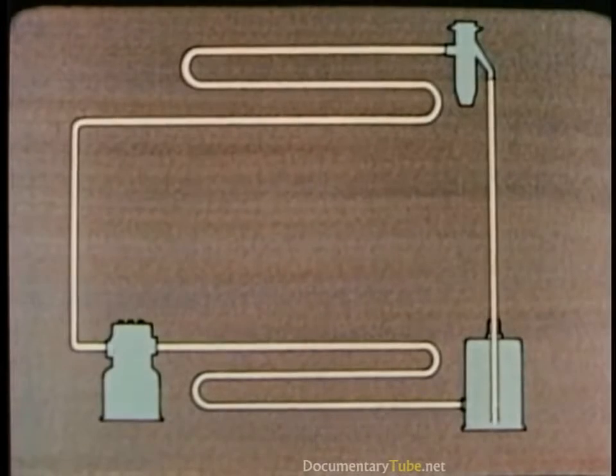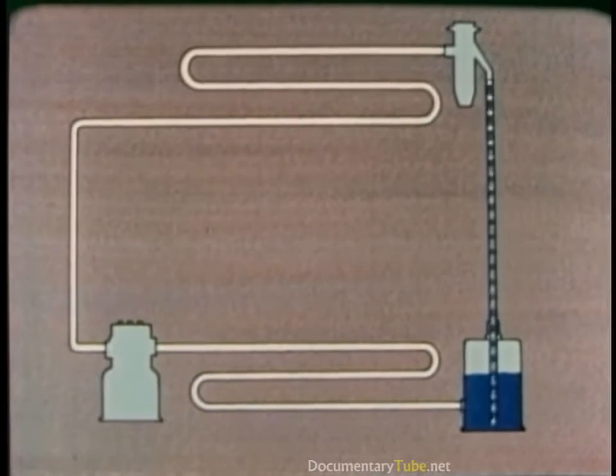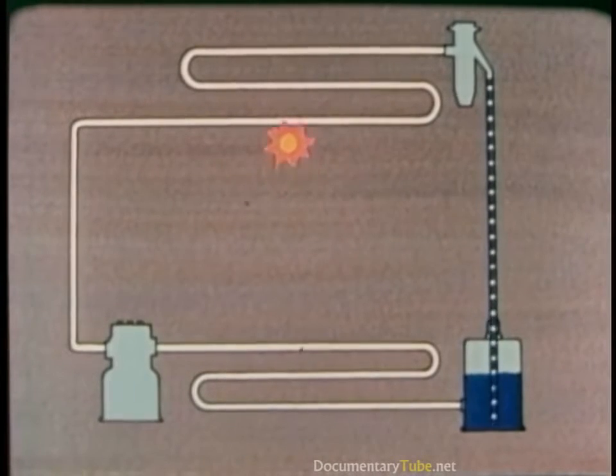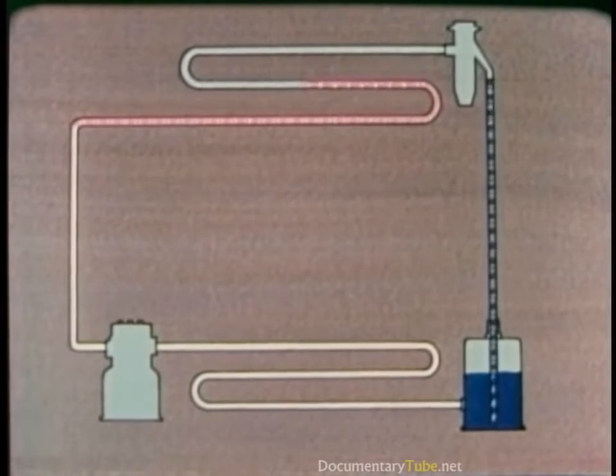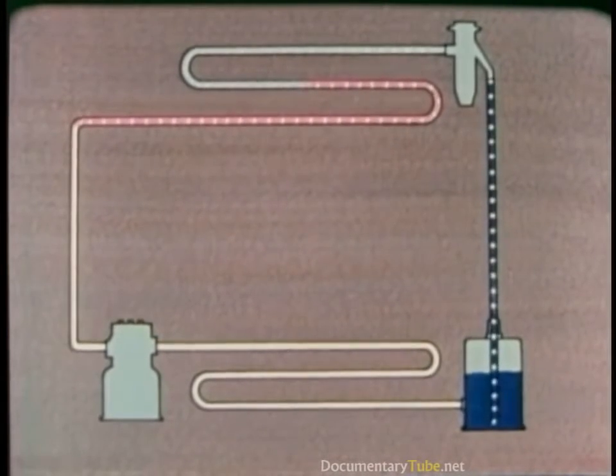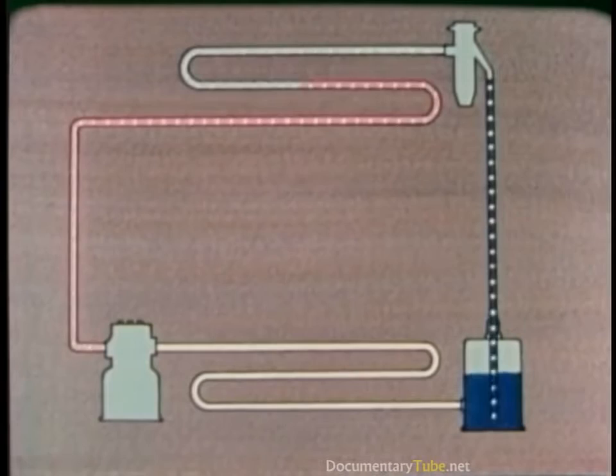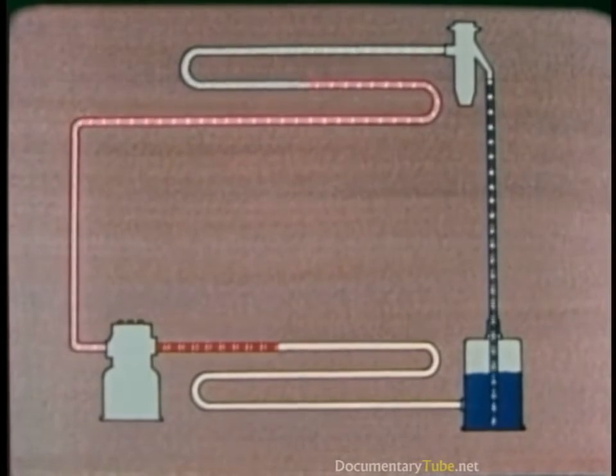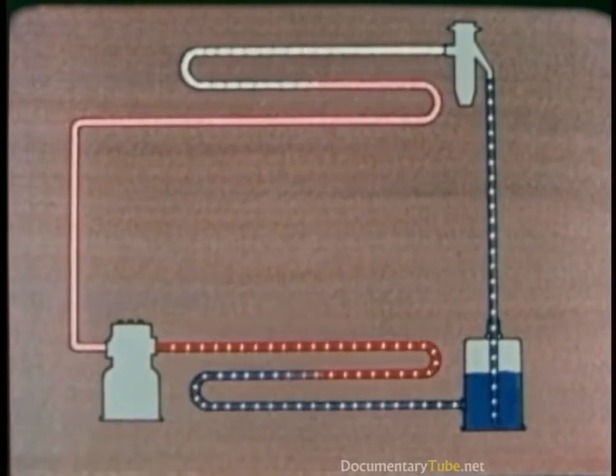Now let's review the whole thing. Refrigerant, under high pressure, flows from the receiver to the expansion valve. The valve causes a pressure drop. The evaporator takes in heat from the box — if anything in the box is hotter than the refrigerant, it gives up its heat to the refrigerant. As the refrigerant takes in heat, it changes from a liquid to a gas. The compressor sucks the vapor out of the evaporator and compresses it, increasing the pressure and temperature. The vapor is now hotter than the surrounding air, so in the condenser, heat is given off to the air. As the refrigerant loses its heat, it changes from a gas to a liquid and flows into the receiver.